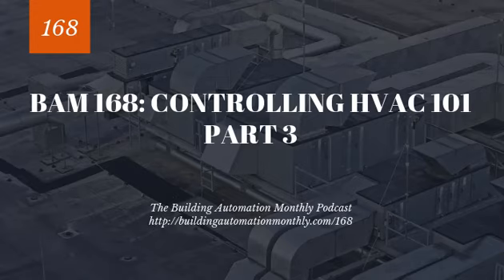There's a variety of different ways load can be calculated. There is the mathematical equation of load, which is looking at temperatures and tonnage and calculating your tonnage versus total tonnage, and that creates a percentage. But realize that sometimes load does not mean the same thing. So you always want to clarify what load actually is when you're talking to someone.